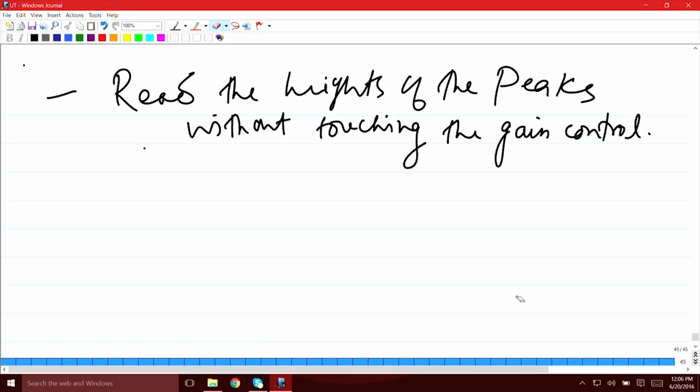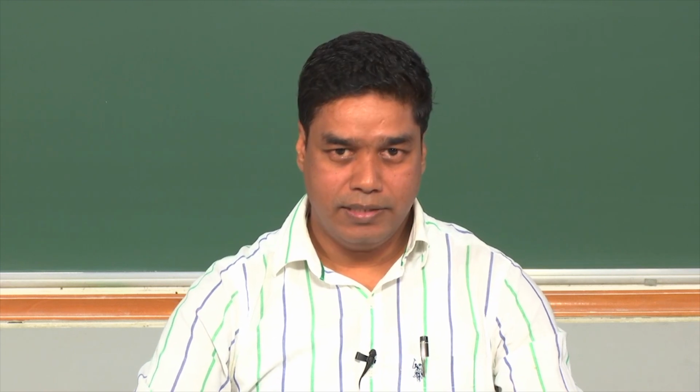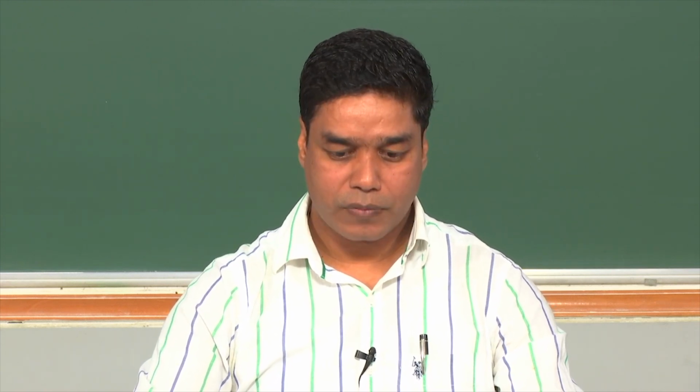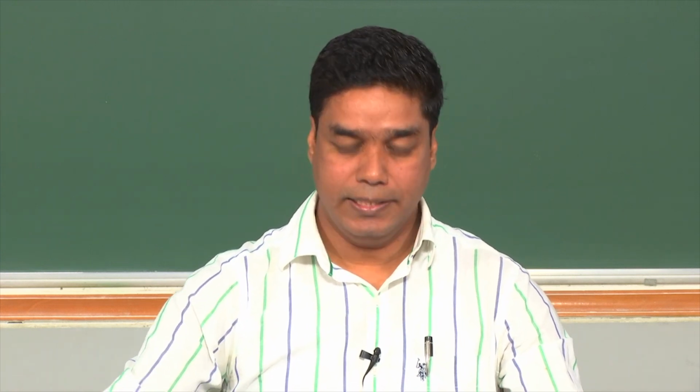So, once you collect the data, the intensity or height of the peaks of the echoes coming out from the flat bottom hole as a function of the distance, then you can take this data and draw a plot. Okay. So, that plot will look like this.